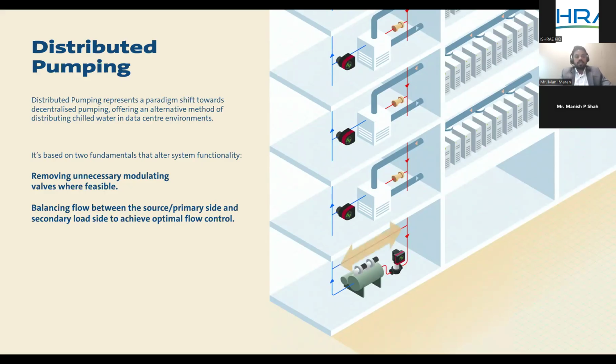The second major challenge in any closed loop system is how to better balance the primary and the secondary side. The primary is the source where we produce chilled water through the chiller, and the distribution side is where we distribute the chilled water to each load. The balancing is what makes the system more efficient. The delta T of the primary and secondary has to be managed and matched to keep the plant room efficiency as close as possible to the most efficient point. These are the two critical components in a traditional system design, and these challenges are addressed with the help of distributed pumping.